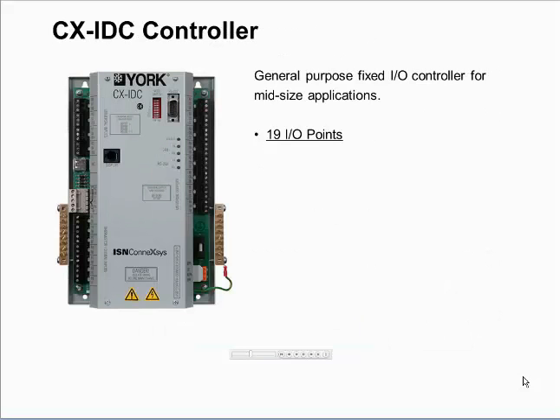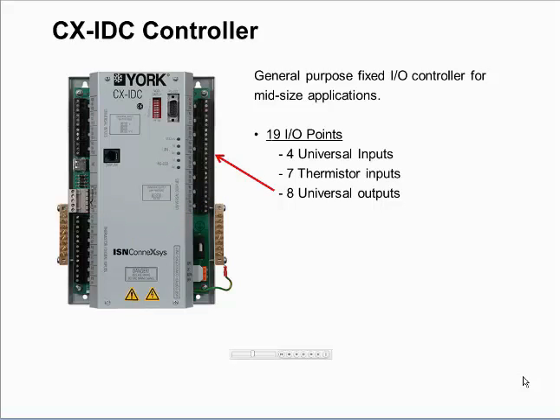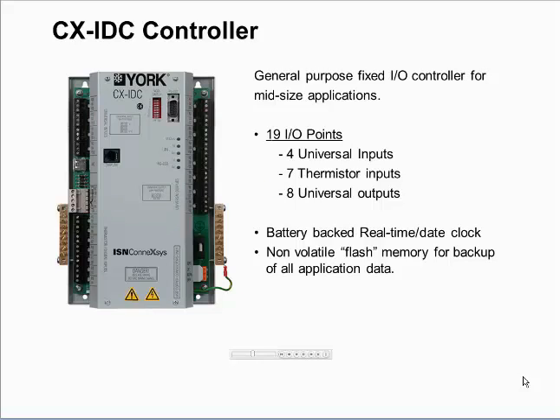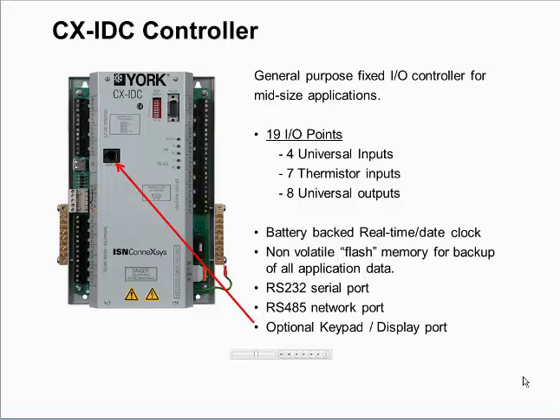The CX-IDC controller is designed for mid-size applications and has a total of 19 I/O points. 4 universal inputs, 7 thermistor inputs, and 8 universal outputs. A battery-backed real-time date clock. Non-volatile flash memory for backup of all application data. An RS-232 serial port for connection of a PC or terminal for programming and monitoring. The RS-485 network port is used to connect to other ISN controllers. And an optional keypad display port.